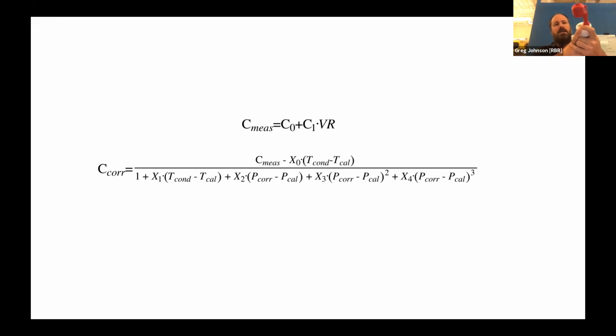However, the first thing to say is that one of the things that drops out of a transformer-based measurement technique is that the cell is completely linear. That is to say, once you've shown that the cell is linear, and it's linear all the way down to 0, which is to say in air measurements, you can actually calibrate with only 2 points. And if you know it's 0 in air, you can calibrate with 1 point. And you only need a single water measurement or a single conductive measurement to do that.